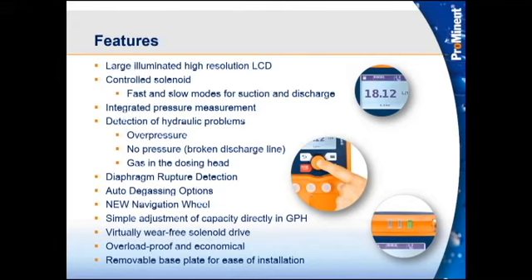How it works is, I'm still working on getting some drawings made up as visual aids for it. But the PVT7 head is the same exact head as your normal Kynar PVDF head. The suction valve is the same. The head block is the same. The only difference is in the discharge valve. If you're familiar with our valves on our smaller pumps, there are kind of 2 cartridges in each valve. Each one of those cartridges houses the valve ball and a seat. So on the discharge valve of the PVT7 heads, the seats are machined a little differently than your typical seats. They actually have really small slots in them. So in both of the cartridges for the discharge, there are going to be 2 slots in that seat.